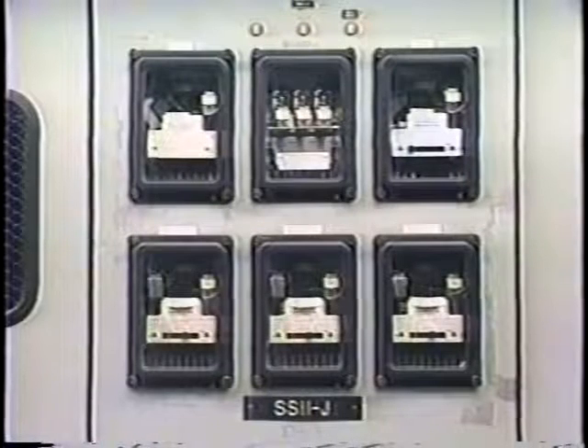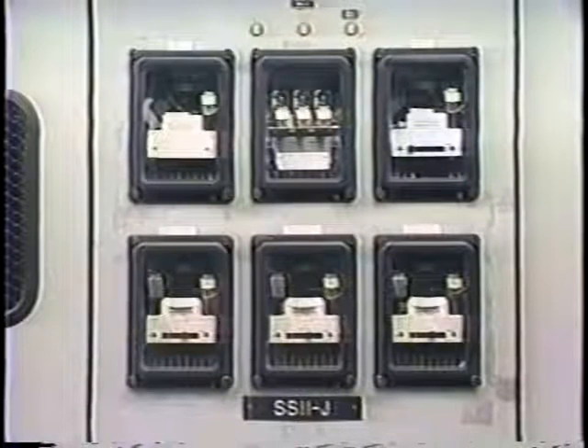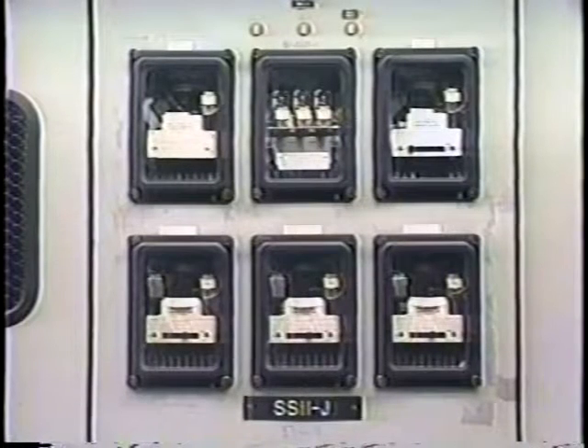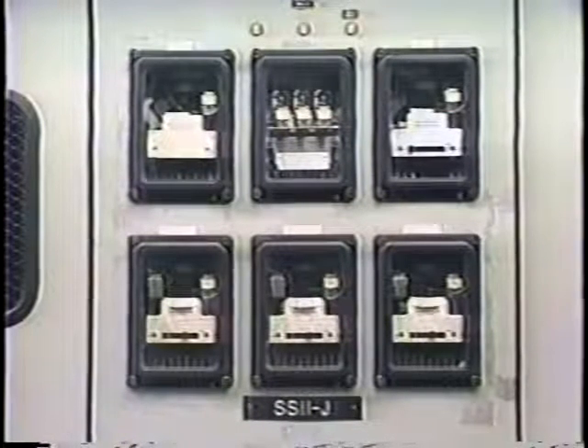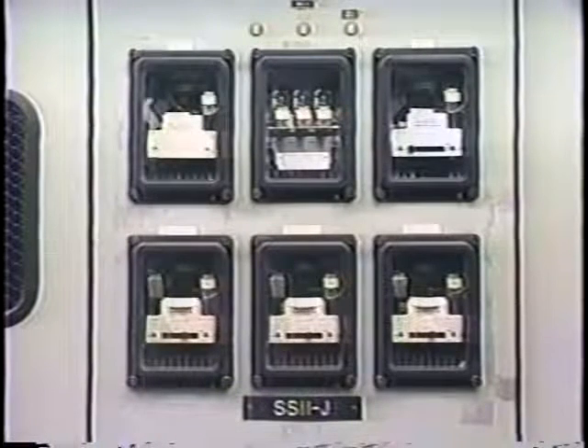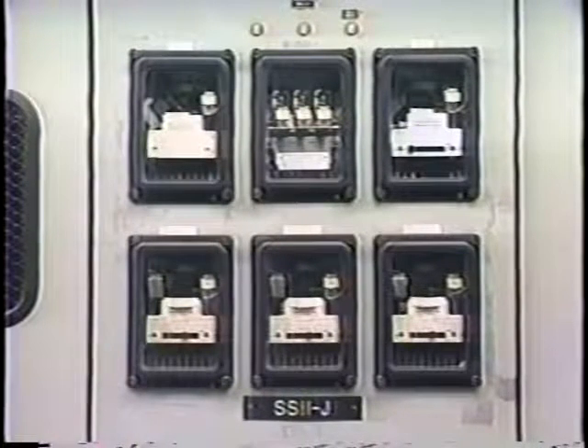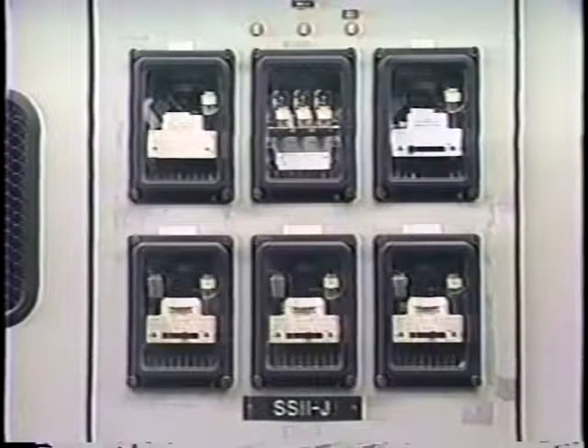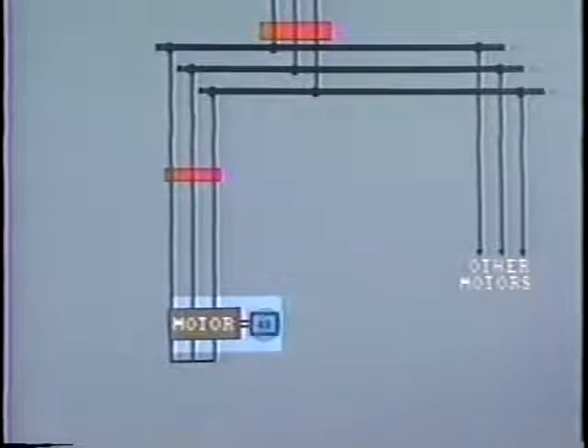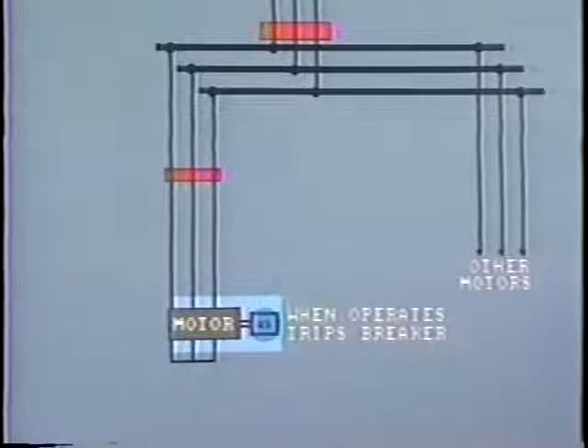Let's look at typical protection relays which would be installed on a 5,000 horsepower motor operating at 4.16 kV. Some of these items are similar to those we discussed in the last segment, but there are several additional relays. As before, we see that overload protection is provided by a thermal overload relay, and for this size motor, this is invariably of the RTD type. When this relay operates, it will close contacts in the tripping circuit of the breaker, and so stop the motor.